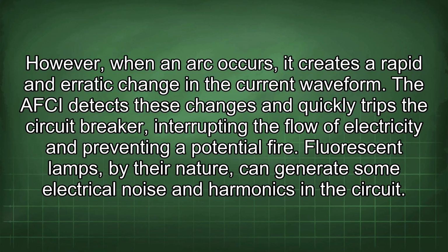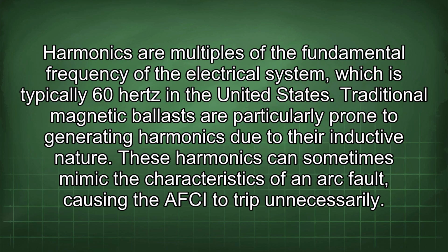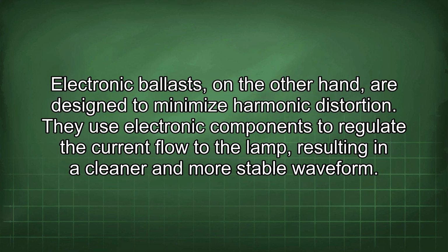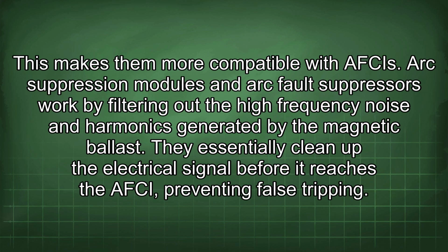Fluorescent lamps, by their nature, can generate some electrical noise and harmonics in the circuit. Harmonics are multiples of the fundamental frequency of the electrical system, which is typically 60 Hz in the United States. Traditional magnetic ballasts are particularly prone to generating harmonics due to their inductive nature. These harmonics can sometimes mimic the characteristics of an arc fault, causing the AFCI to trip unnecessarily. Electronic ballasts, on the other hand, are designed to minimize harmonic distortion. They use electronic components to regulate the current flow to the lamp, resulting in a cleaner and more stable waveform. This makes them more compatible with AFCIs.